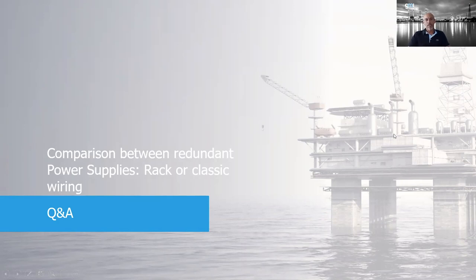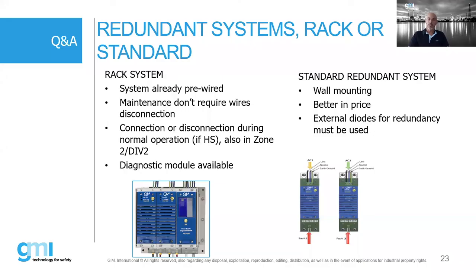Comparison between redundant power supplies, rack, or classic wiring. You can have a redundant power supply in a rack, or a standard power supply in a DIN rail version with the ring solution. So the rack system is already pre-wired, so you don't have to connect the power supply. The maintenance doesn't require wire connections. Once you want to remove a unit for maintenance, for replacement, whatever, you don't need to disconnect the wires. Disconnection or connection is also possible during operation if you use the hot swapping solution, also in Zone 2, so in hazardous areas. And the diagnostic is available only for the rack systems.